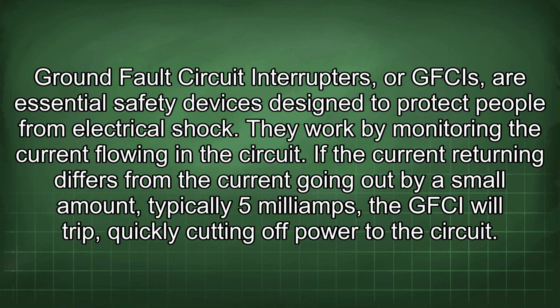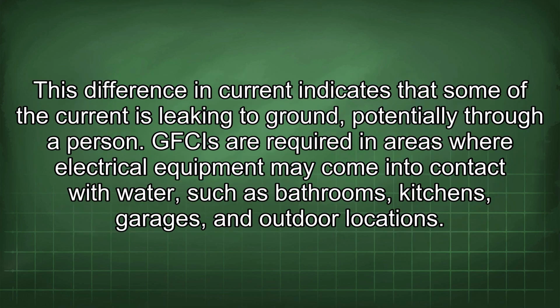Ground fault circuit interrupters, or GFCIs, are essential safety devices designed to protect people from electrical shock. They work by monitoring the current flowing in the circuit. If the current returning differs from the current going out by a small amount, typically 5 mA, the GFCI will trip, quickly cutting off power to the circuit. This difference in current indicates that some of the current is leaking to ground, potentially through a person. GFCIs are required in areas where electrical equipment may come into contact with water, such as bathrooms, kitchens, garages, and outdoor locations.